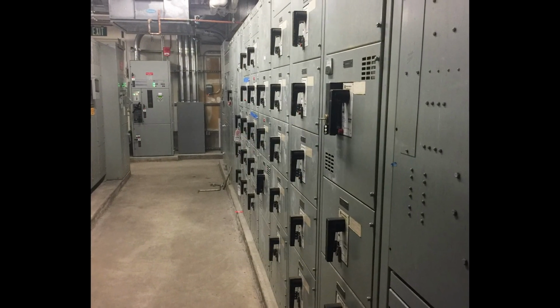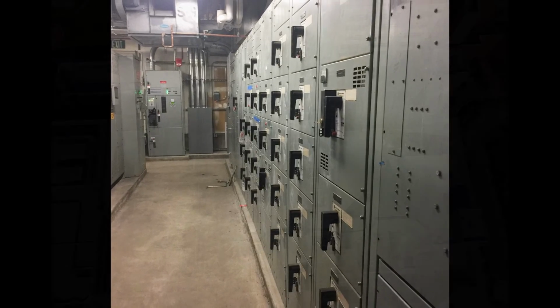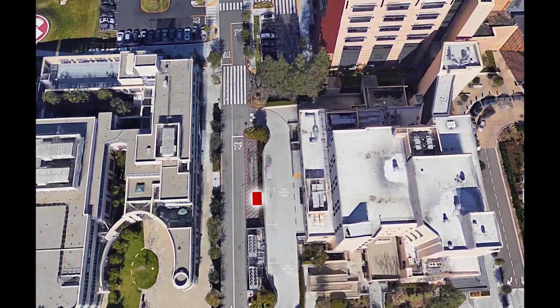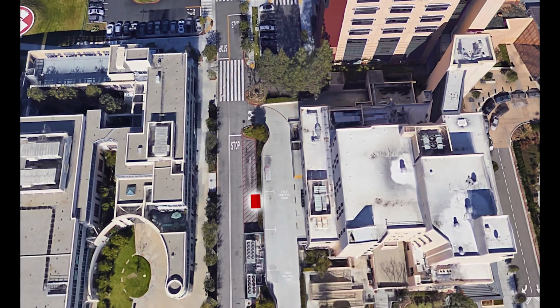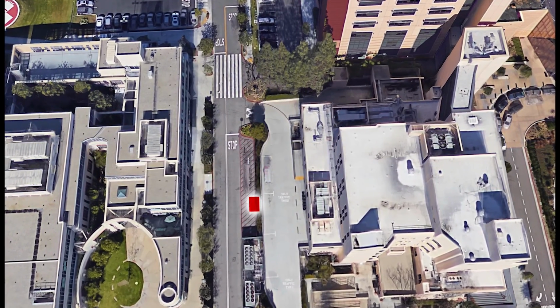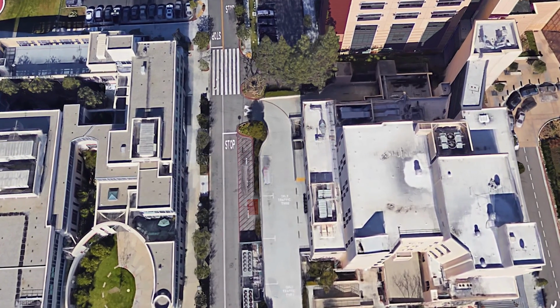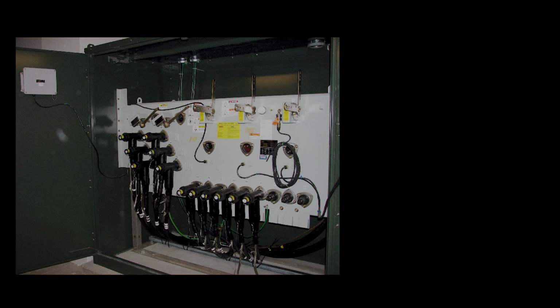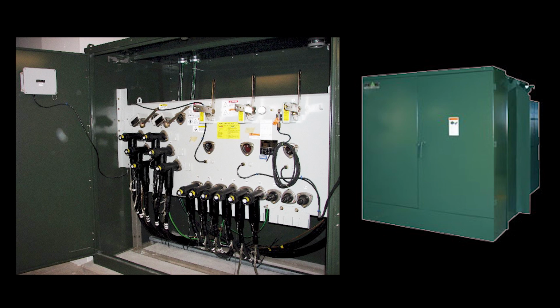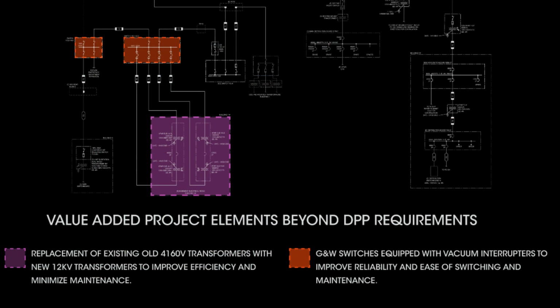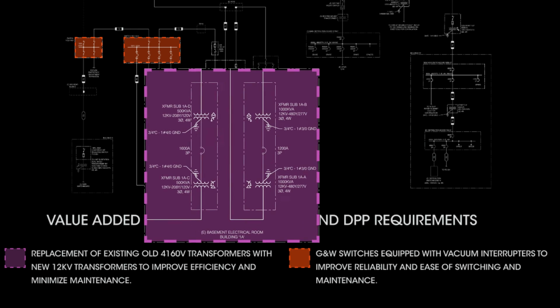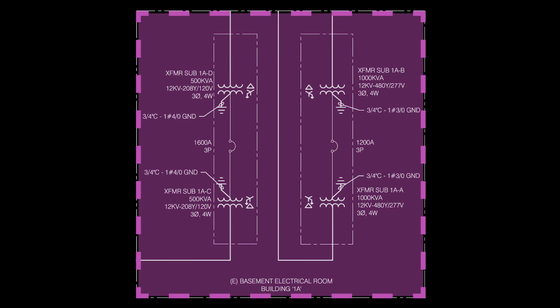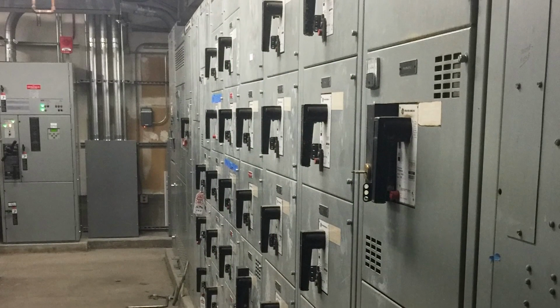Our proposed design replaces the existing old 4160 volt transformers inside building 1A rather than provide additional 12 kV transformers outside of the building to improve both efficiency and minimize maintenance. Our design minimizes equipment outside building 1A by placing equipment inside building and provides dedicated switches equipped with vacuum interrupters to isolate individual transformers in building 1A. The provision of G&W switches with vacuum interrupters in place of fuse switches will improve reliability and ease of switching and maintenance. Power interruptions will be minimized by replacing 1 transformer at a time while keeping the 2nd transformer of the double-ended substation operational.